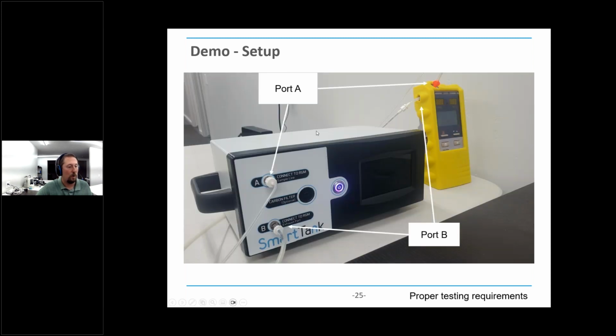So again, the best way to learn is through a demo. Before I get switched over to the live version, I do want to orient you on my setup. I have this SmartTank sitting here. It's sitting next to this yellow capnometer, which is a microstream device. It's actually the same technology that's in a Philips 3015A device. This port, this sample line, is connected over here to A, and this exhaust line is connected over to B. You'll see there's nothing else connected between them. There's no other devices, and these connections will remain the same throughout the demo, even though I'm going to do different things with it.